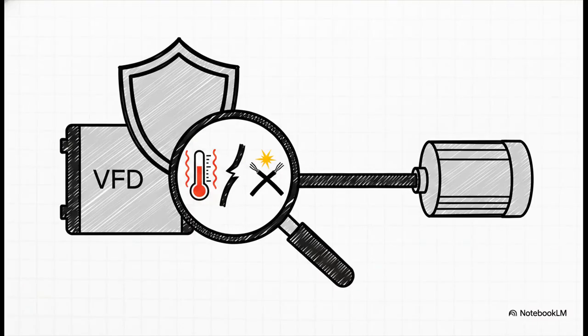And you know what I genuinely love about this built-in PTC management? It's the smart fail-safe technology. Once you've got it wired and enabled, the ATV320 isn't just passively looking for motor overheating. The drive is actually smart enough to monitor the integrity of the safety circuit itself. It'll trip the drive if it detects a broken wire in the sensor line, or even if it detects a short circuit in the sensor. It is just incredibly robust.